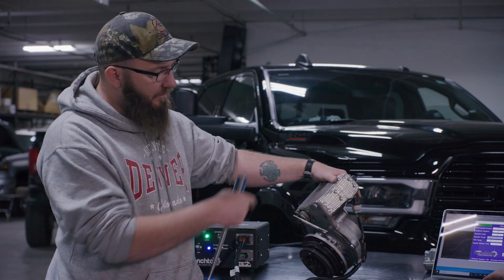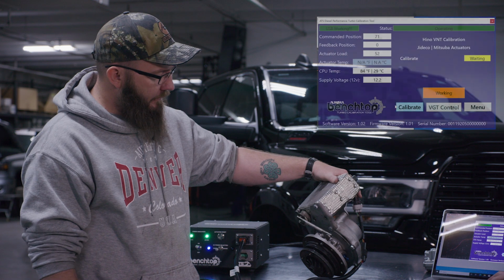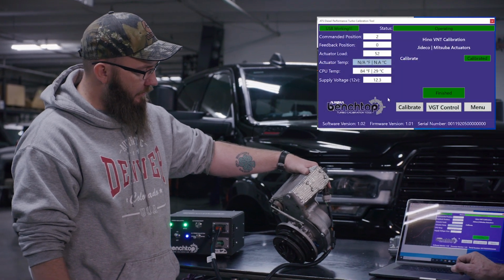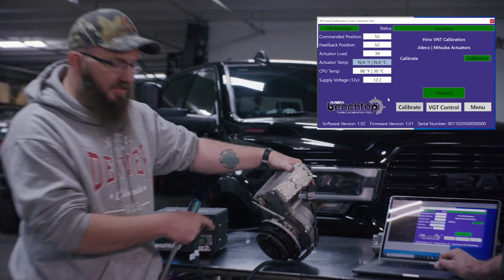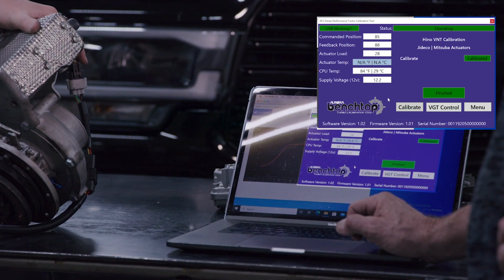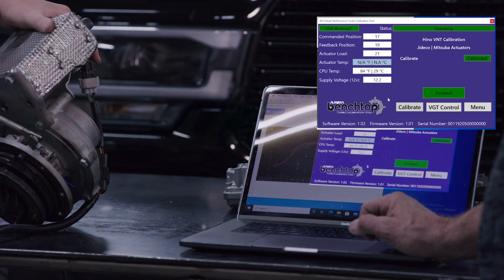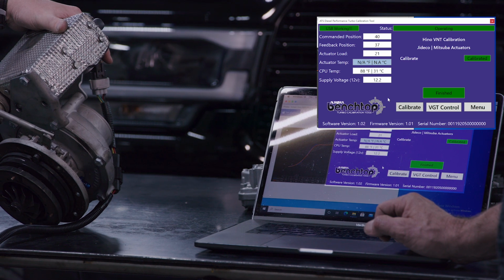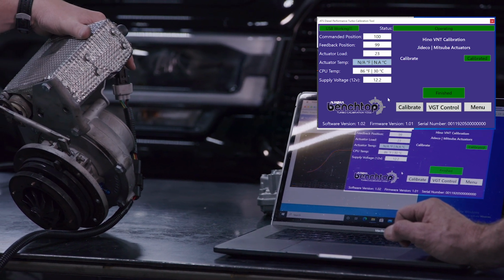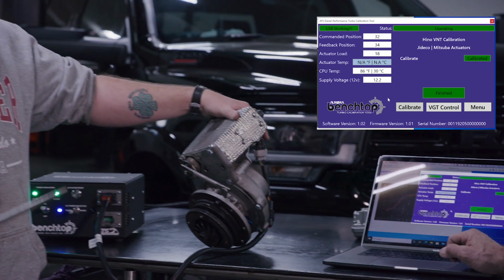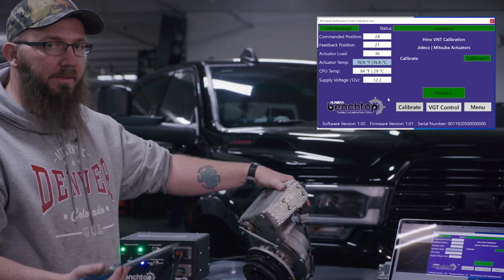Now if we run it again, recalibrate, you're going to see it's going to have that full range. This is why, like I said, you have to calibrate actuators. Just because it bolts up, it says operating, it seems to be working, does not mean it's calibrated to that frame. You have to calibrate it to the frame of the turbo.